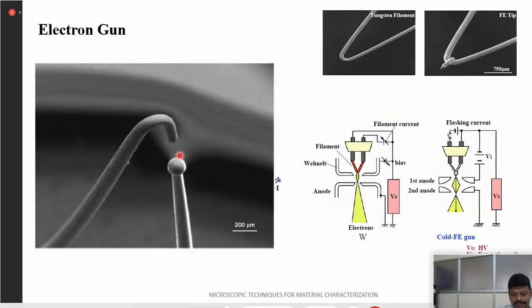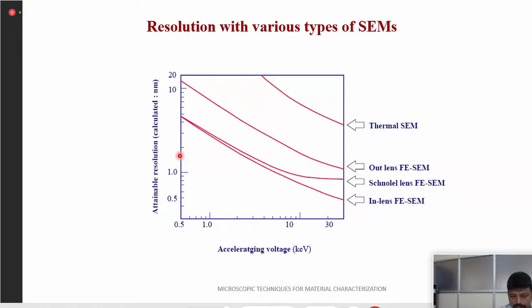And the resolution with various types of SEM. You can see the thermal SEM. Thermal SEM means thermionic emission SEM, with a tungsten filament. You can see the resolution point and the acceleration voltage at the bottom. The resolution point is very low for thermal SEM, and in-lens FESEM is giving better resolution. And even with different types of lens systems, we'll get better resolutions.